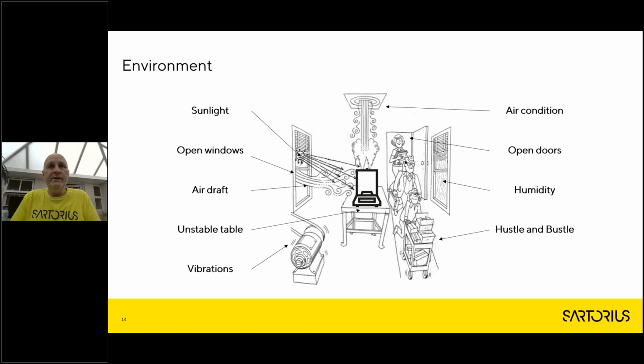So what about our environment? If we think about our laboratory where we're placing the balance, is there sunlight, direct sunlight coming through the window towards the balance? We all know that balances are made up, particularly the weighing cell is made mainly of metal. So that weighing cell is going to expand and contract according to the ambient temperature. So if we have direct sunlight on the balance, heating the balance up, that will expand the weighing cell and create an error. The balance will then need recalibrating. Do we have open windows? Open windows will create a draft, an airflow.